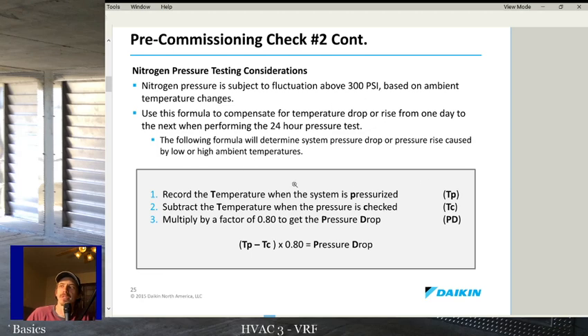So you can use this formula to compensate for temperature drop or rise from one day to the next when performing a 24-hour or longer pressure test. Make sure you always record the temperature of the piping components when you do this. So if most of your line set is in a temperature controlled building, like the building already has air conditioning in it, so most of the line set stays at 70 degrees the whole time, you probably won't notice much of a pressure change, right?